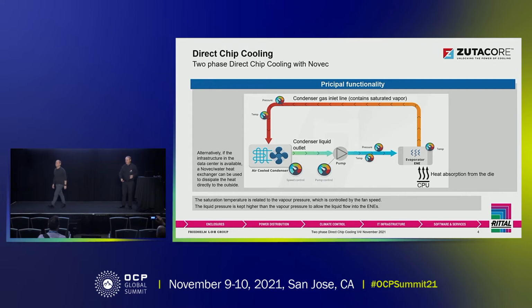What we would see in a system like this, we call it two-phase cooling, is that the evaporators, the cold plate, instead of just being liquid in, liquid out, the liquid comes in, it boils inside the evaporators, and then it goes to a condensing unit - some call it CDU, we call it HRU, heat rejection unit - that condenses the vapor back into liquid and pumps it back into the system. So a very simple loop creates this cooling effect that is needed on every single chip.